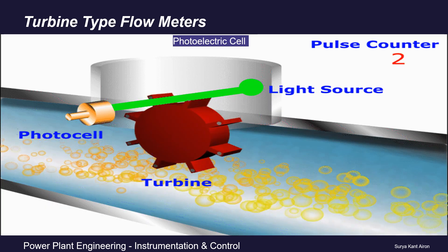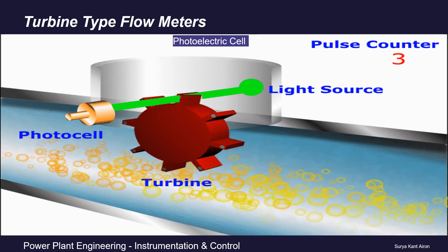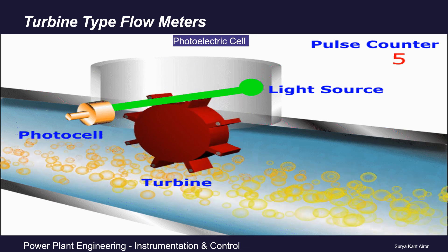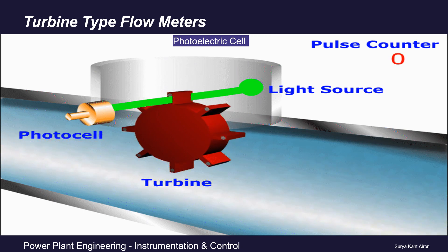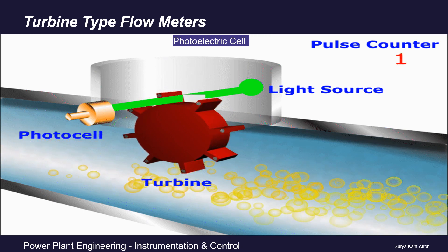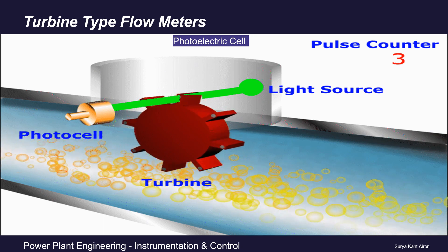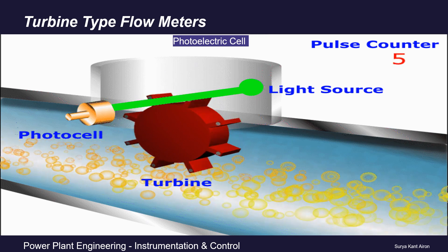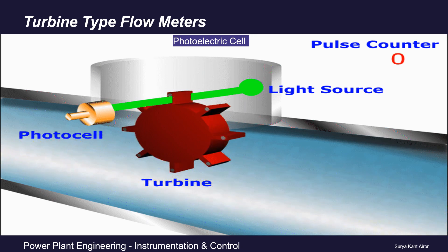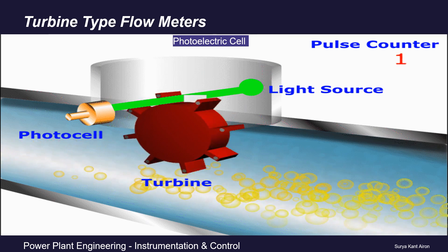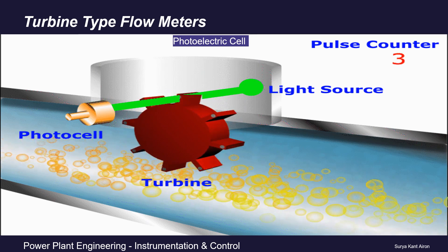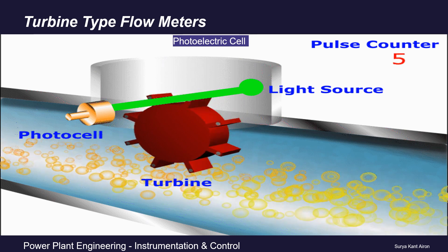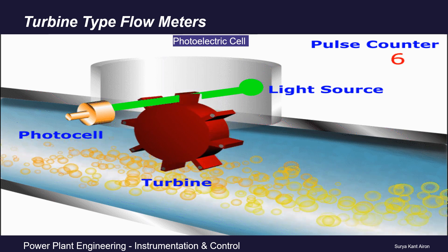The next type is a photoelectric cell. A photoelectric cell also senses the motion of the turbine blades and is comparatively very simple. Instead of indirectly measuring an induced current, the sensor produces an electrical pulse as each blade passes through the sensor. The pulses are counted or totalized over a time period to determine the rotational velocity of the turbine.